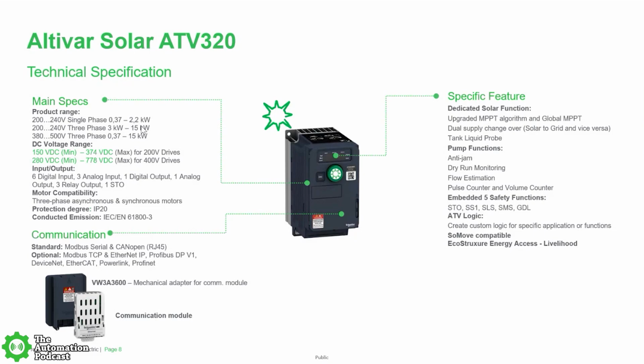It's going to go from single phase 230, three phase 230, and three-phase 480 volts up to 20 horsepower. And the DC voltage ranges are right here. This is kind of key to know the DC voltage ranges because, as we will see in the next few slides, that's really going to dictate the maximum current that we can put into the motor. We have our 6 digital IOs, 3 analog inputs, 1 digital output.